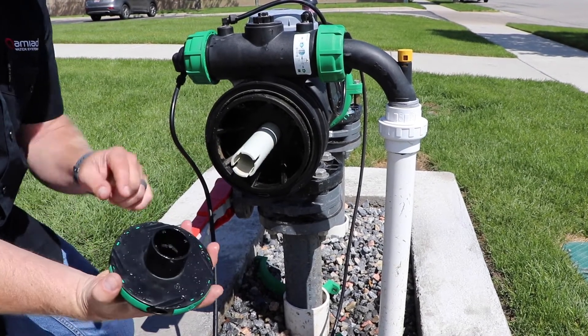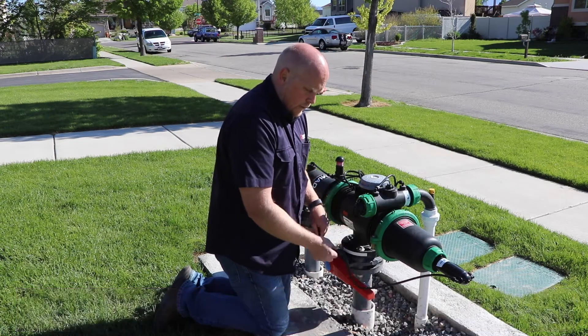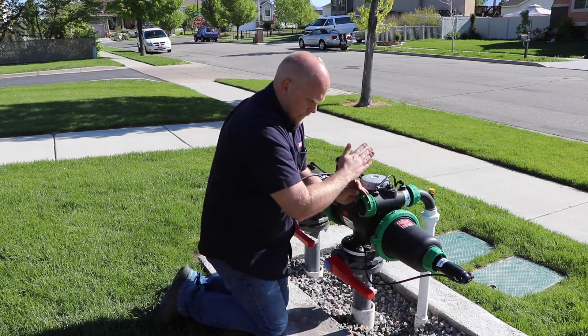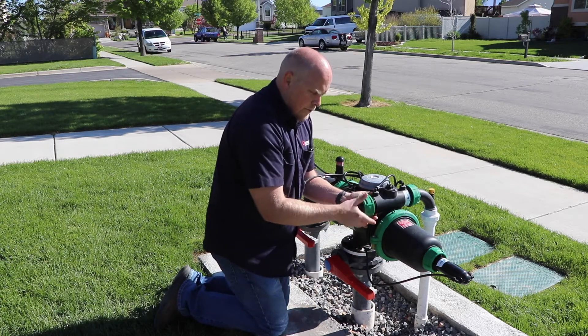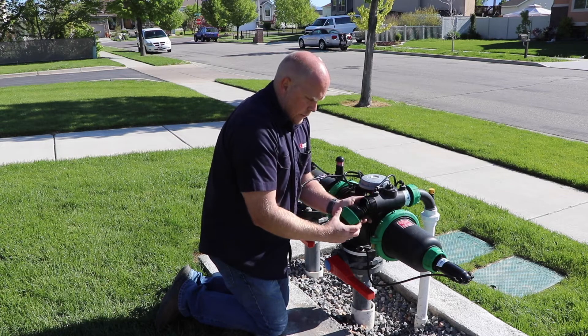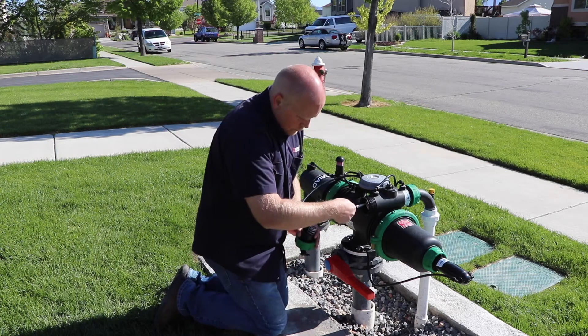When we put our drive mechanism back on, it slides on and we freely move. Now we want to show you how to take apart the valve and also how to put it back together properly. Take the two tubes off, loosen the nut here. When it comes off, there is a spring inside of this, so you want to make sure that the spring stays in and doesn't pop back at you. When it comes out, you'll have the spring right here. Then to get to the piston, you'll want to get a pair of pliers.